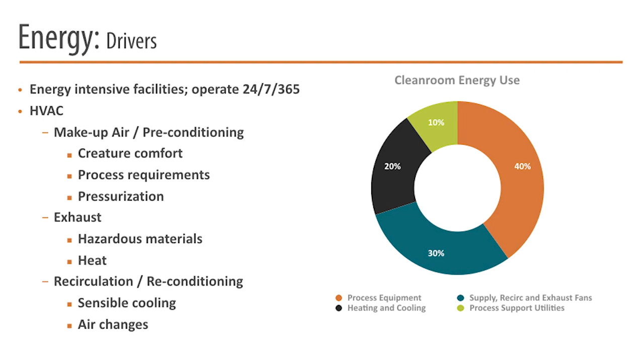Humidification is part of that, and the air you need for pressurization, which goes hand in hand with exhaust—how much you're putting into the space versus pulling out. The number and types of exhaust streams are dictated by how hazardous the material is that you're pulling out. Generally you'll have corrosive exhaust and solvent-based exhaust, and you might need abatement and other environmental measures to contend with this. Then there's local reconditioning for sensible cooling—how you continually remove heat from the space. So that's half of the energy in your clean room.